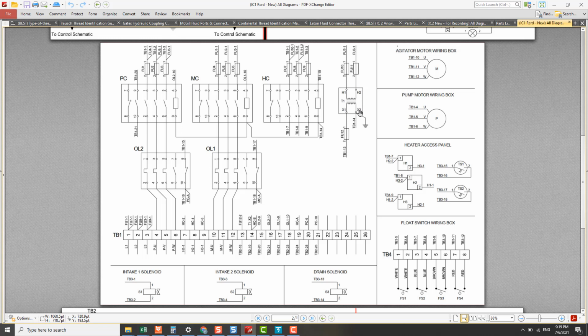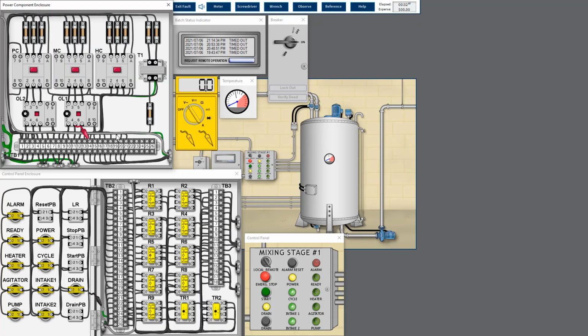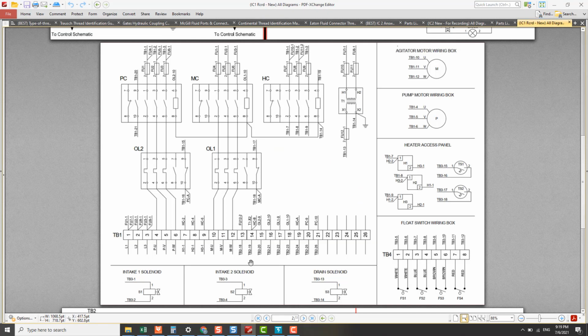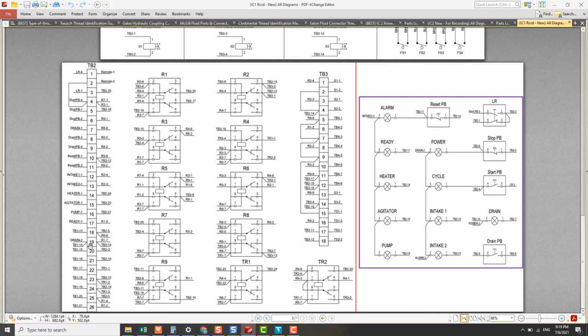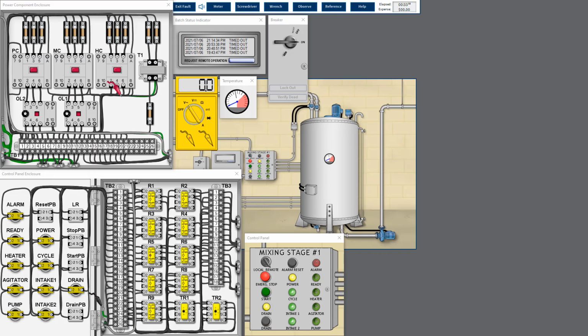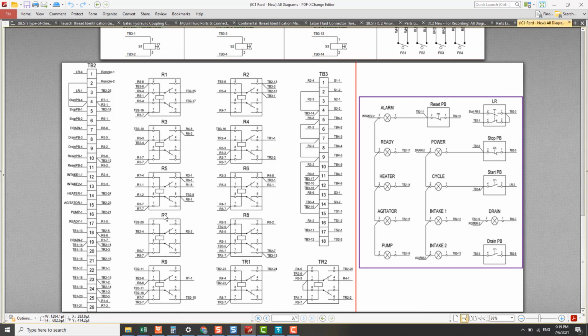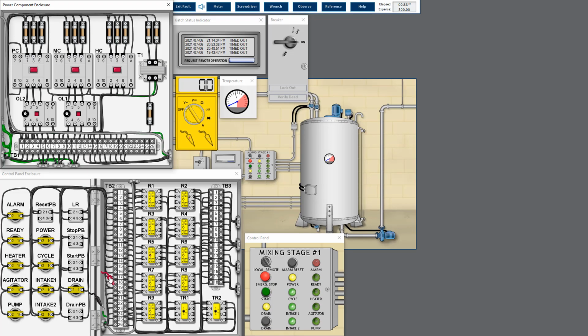Now the black probe is at the ground point, which is connected to the neutral point. The red probe we measure at TB114, which is connected to here. We must achieve 0 voltage. This one is actually connected to HCB, which means heater contactor point B, and we can connect to here, heater contactor point B. 0 volt is correct. Then it is connected to TB219. TB219 is here, and we measure 0 volt at TB219. Good. TB219 is actually connected to drain 2. Here, drain 2 lighting, 0 volt is okay.